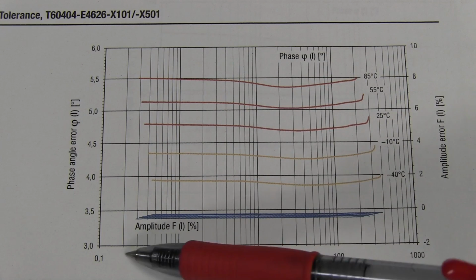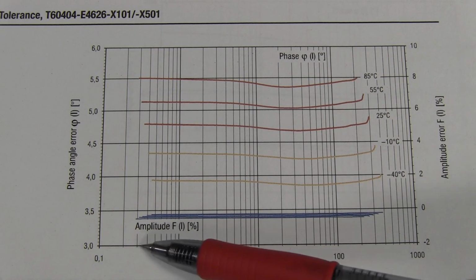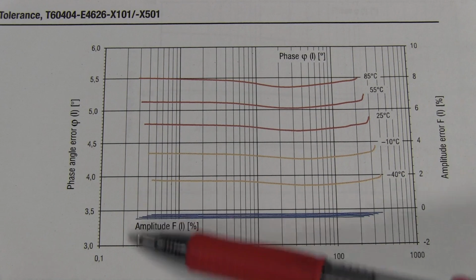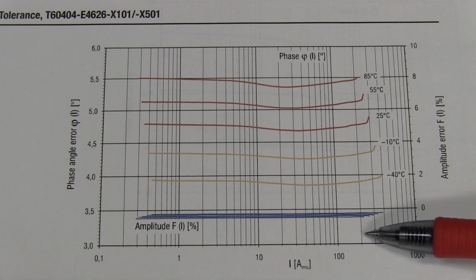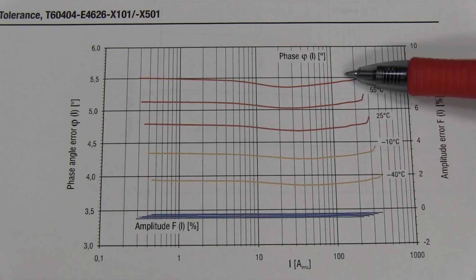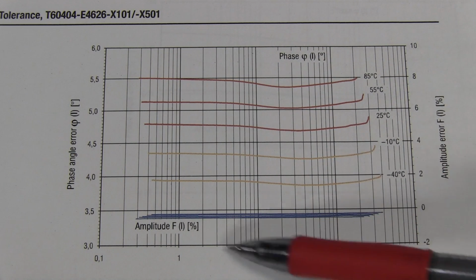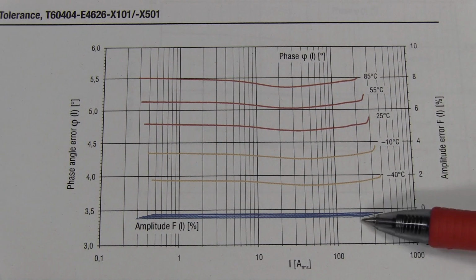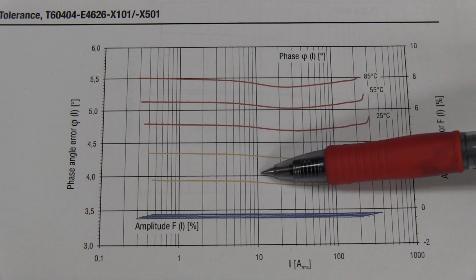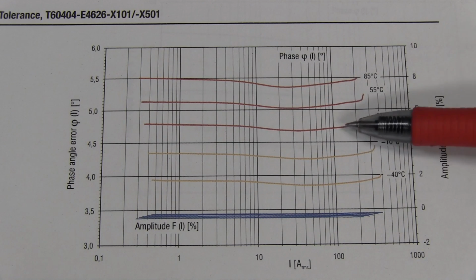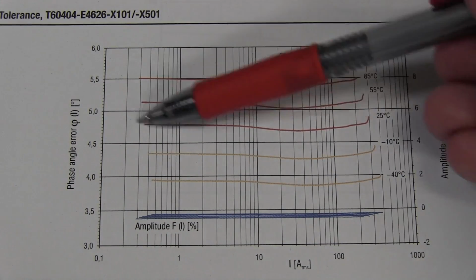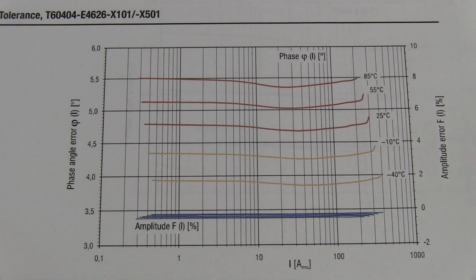And here's the characteristic curve graph, showing various things versus current. The graphs extend from a couple of hundred milliamps all the way up to a couple of hundred amps. So this one's only rated to 100 amps, but it can obviously go a bit beyond that. You can see the amplitude error here, a tiny little amplitude error in percentage, and that basically does not change with temperature at all. But the phase angle does obviously change with temperature, so that would be calibrated, or they'll try to calibrate it out at a nominal temperature. Still, it's pretty good over the entire current range. I really like it.